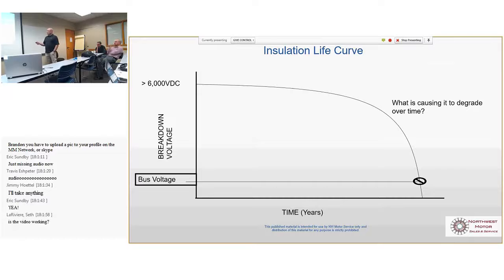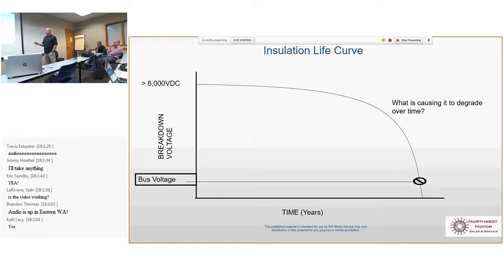So we're testing first at the bus voltage. You're at 500 volts, and that's how we step it up clear to 2,000 on your 480 volt motor. So this is your window of opportunity to find a problem before it blows up on you.